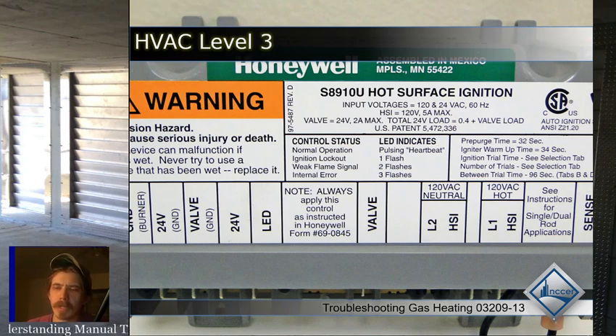So if you think you're having an issue and you think it's the thermostat, which is actually pretty rare, but thermostats can fail, what you want to do is take the thermostat off the wall and then jump the wires as if you're making the thermostat switch, right? So if you're trying to call for cooling, you jump R to Y at the thermostat and see if everything works. R to G to run the indoor fan, see if everything works. R to W for heat, see if everything works, and so on and so forth. And remember, with a heat pump, you're going to have to power O if you want cooling on, right?